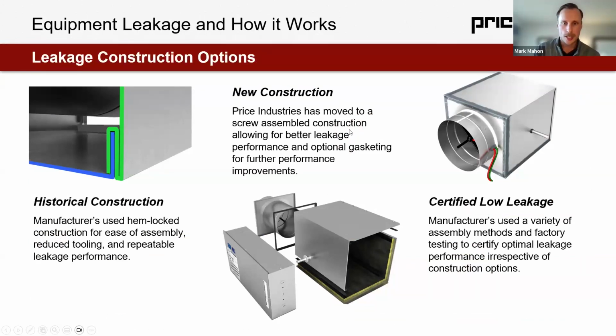The new construction is one that we've kind of improved upon. It uses gasket and screws. And so that's our new construction. Big reason why we're using this new construction is because long-term, the goal for us is actually a different single duct construction that's going to perform better. We're going to be releasing a new fully reconfigured single duct this spring. That's going to be a higher pressure class because of the damper position. And so that's something to make note of. And that's why we're transitioning to this casing construction instead, which performs better.